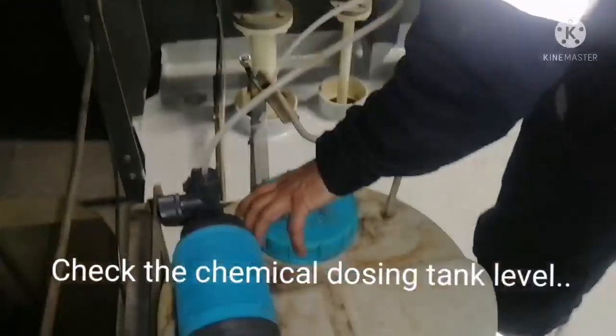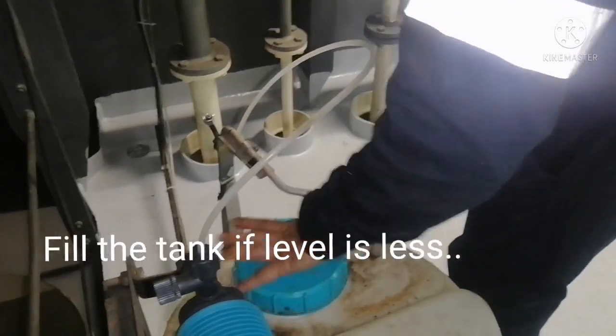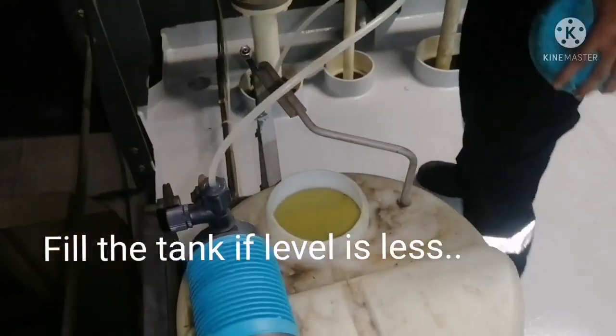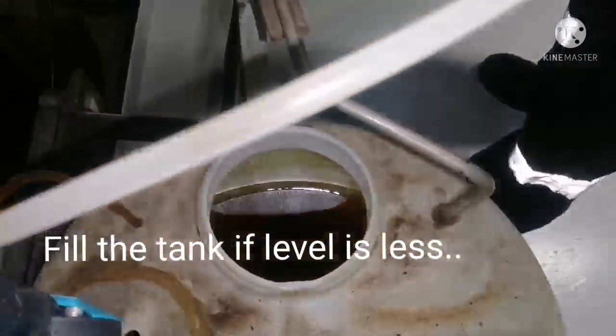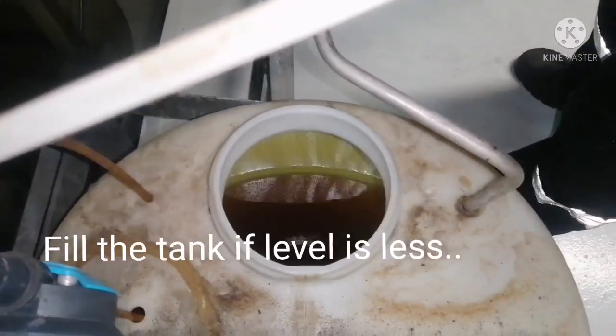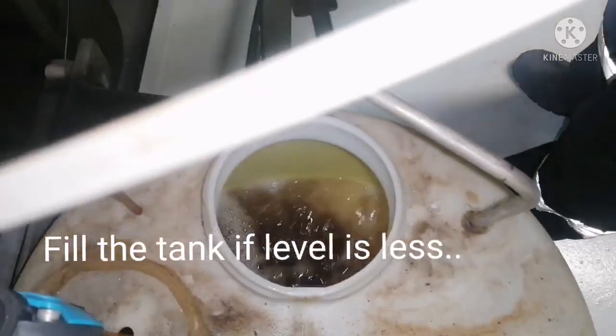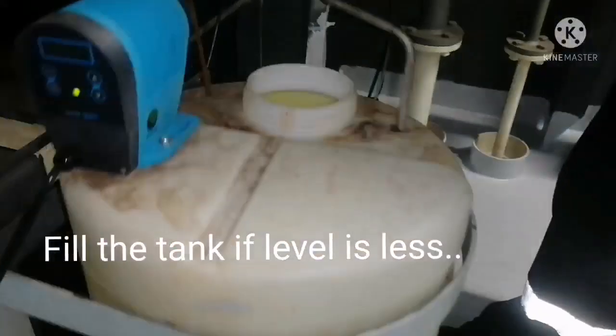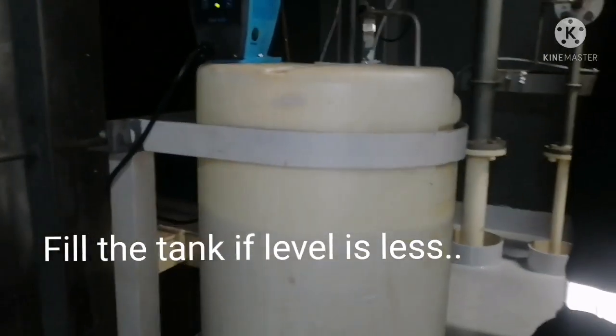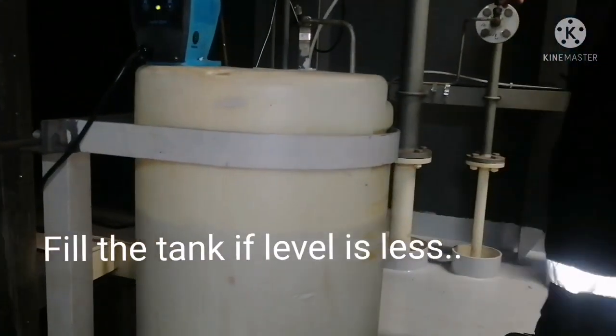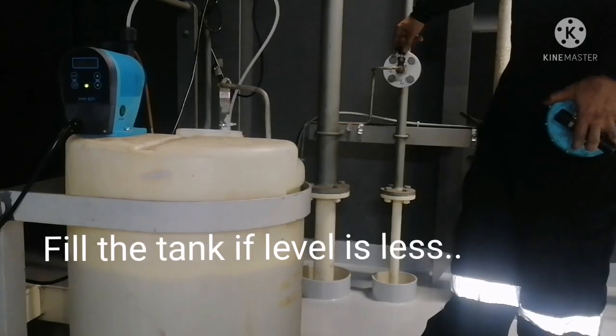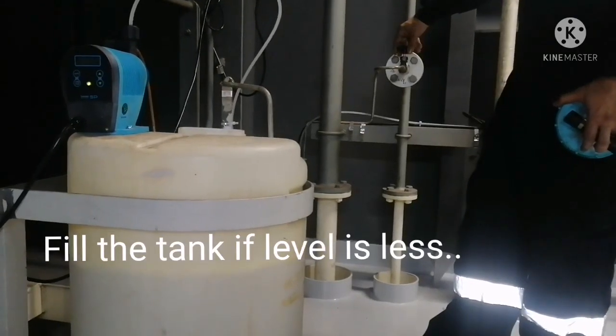And also you have to check the level inside the dosing tank. If the level is low, you have to fill the water by adding chemicals. So this is how you have to fill the water. Usually most ships have a direct freshwater line which connects to the dosing tank.